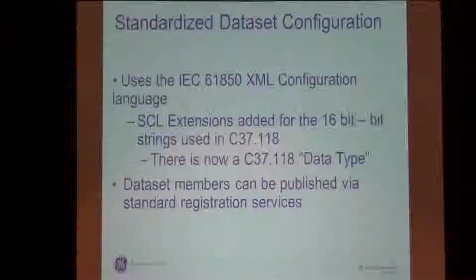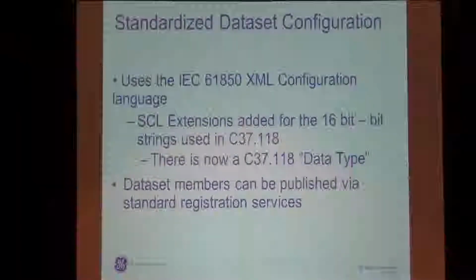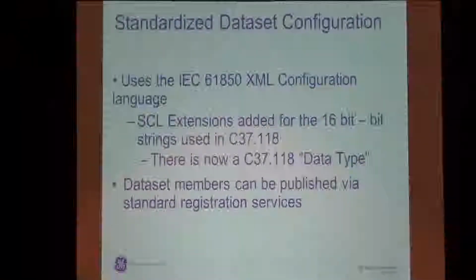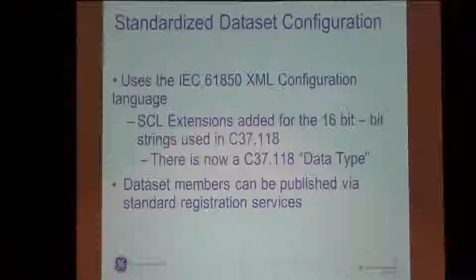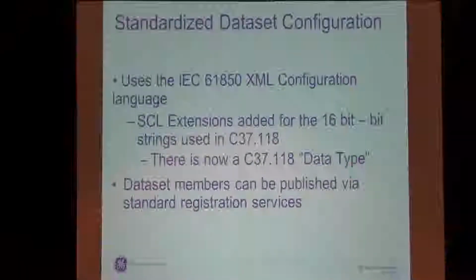What this does allow going forward is the ability to do remote configuration using the substation configuration language tool that Ralph talked about earlier also. So a PMU can now export an IED capability description file. This file can now be used to configure any upstream device that will be receiving this data set.